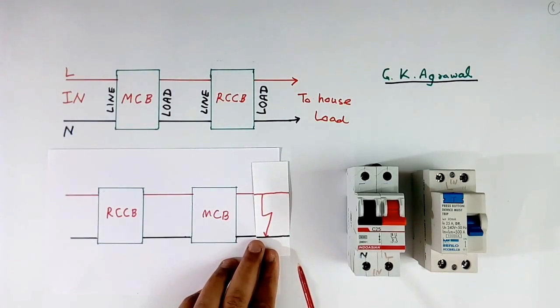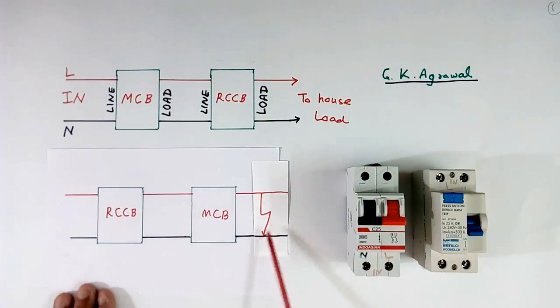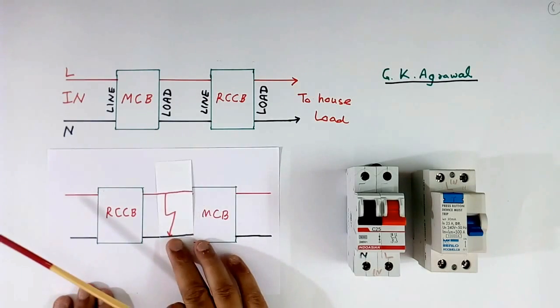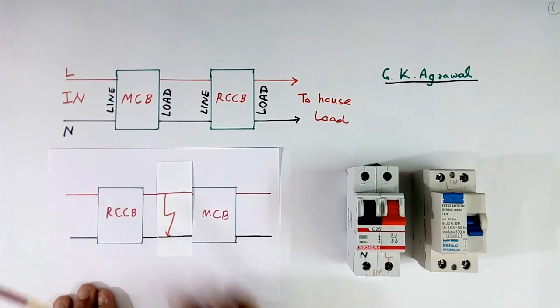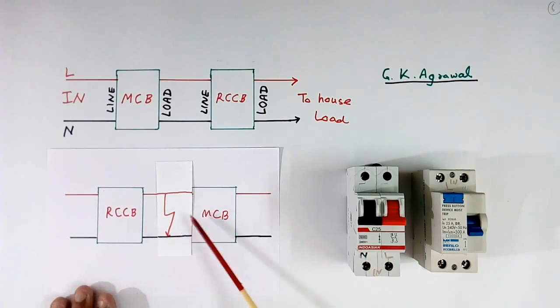But in this case, if fault happens here, then fault current will flow in MCB. It will protect. But if fault happens here, like this, so this fault current will not flow in MCB and MCB will not protect.